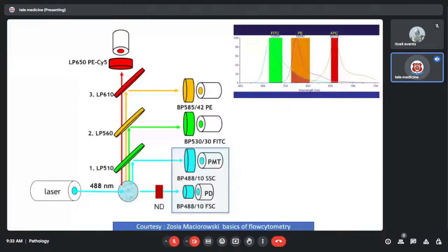This is the basic model of the flow cytometer. ठीक है? This is the laser beam or the light source, and this is the object or a cell which is passing through. Here, so what happens? Whatever laser beams come and strike this object, some will come and strike this neutral density filter. So I told you the purpose of neutral density filter is that it will block some amount of light and allow only part of it to pass through, so the detector here doesn't get saturated.